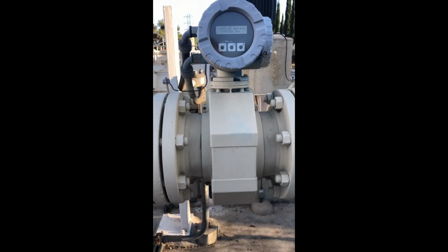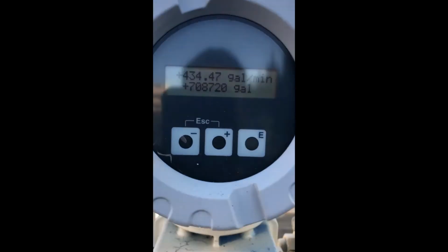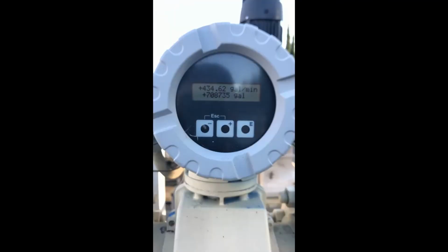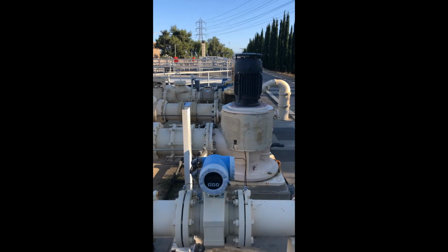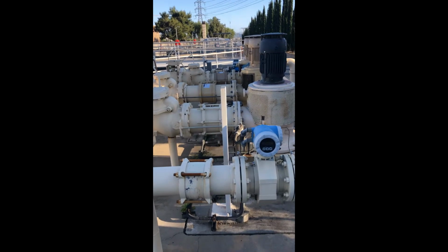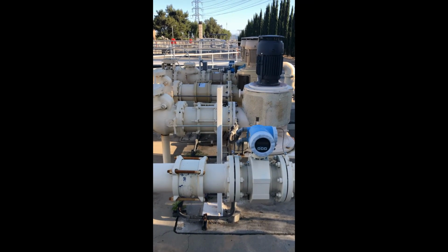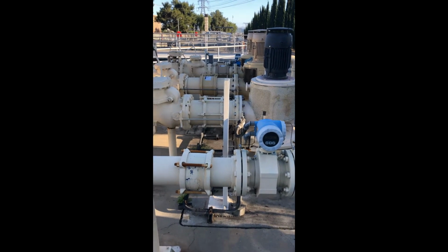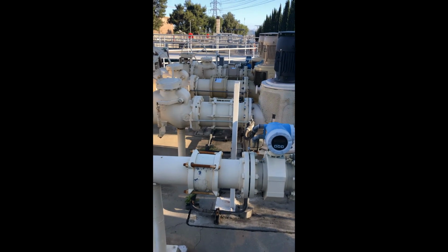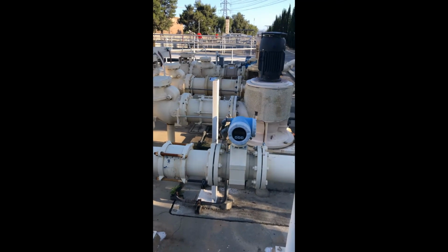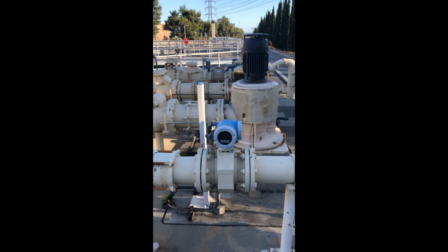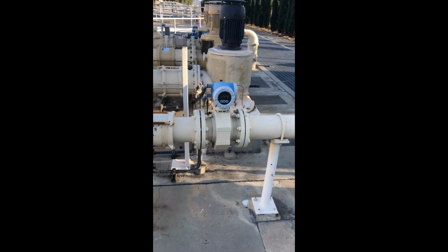This is the mag meter for the return activated sludge. And so this is where we get our process variable. On SCADA, we will put the percentage of how much we want to return of plant flow. Okay. Say, I think we'll see when we go in, I think they usually return about 20 to 30% of what the plant flow is.